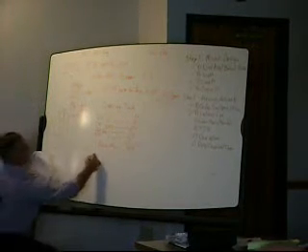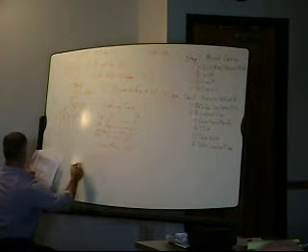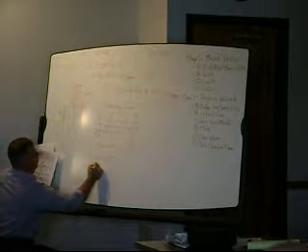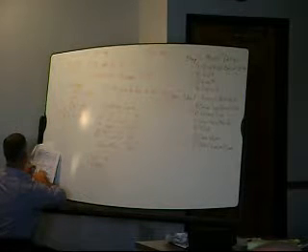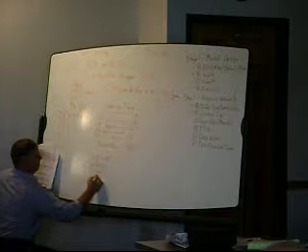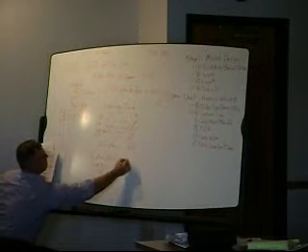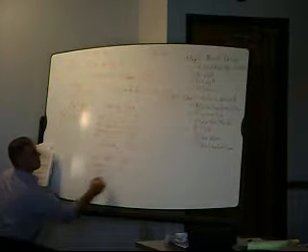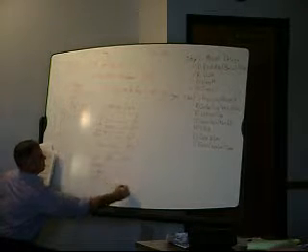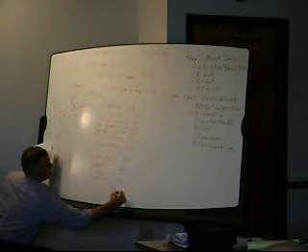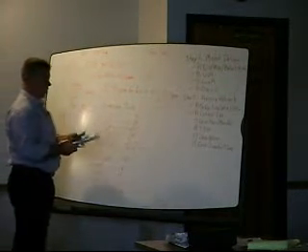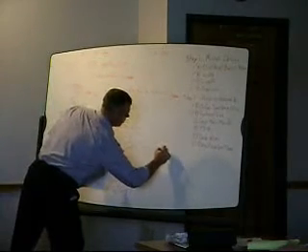Now when I get to the force main, straight pipe, 185 feet. We've got 4 45-degree elbows, 1 T, and 1 gate valve. So straight pipe, 185 feet, 1-to-1. A 45 on 2-inch pipe, what do we got? 16 feet. T? 11 feet. Gate valve, 1.4. So we add all that up. There's all the pipe and equivalent pipe lengths that went through. Add all this together. There you go, 254.8, the number there.